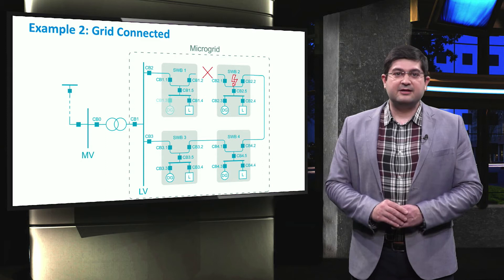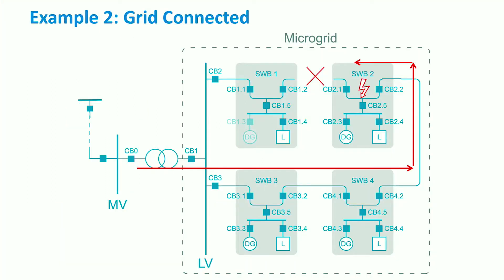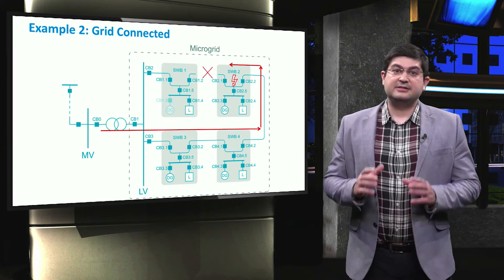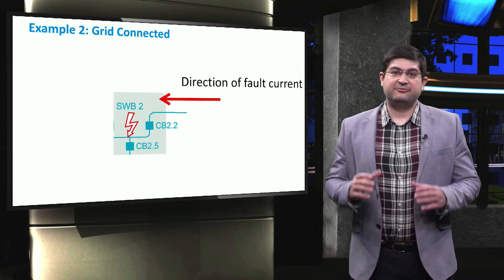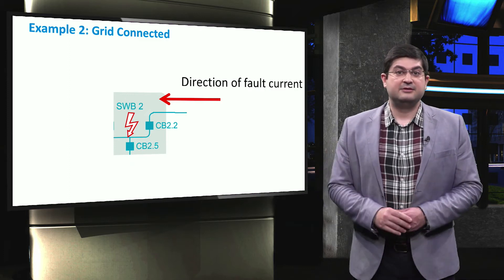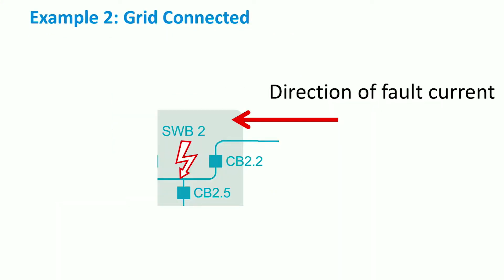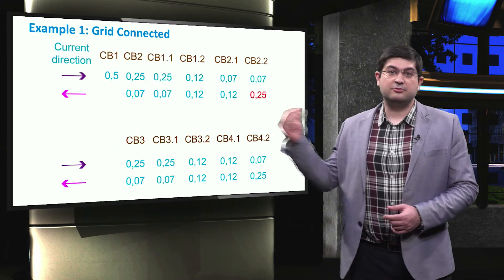Now let's assume that a second fault occurs inside switchboard 2. In this case, the fault current is provided again through the external grid, but unlike the previous example, the fault current is supplied by the feeder below. The fault current will be from the right-hand side to the left-hand side direction. Typically, if directional relays are used, then the setting of the tripping time will be different in various directions — from left to right or from right to left.